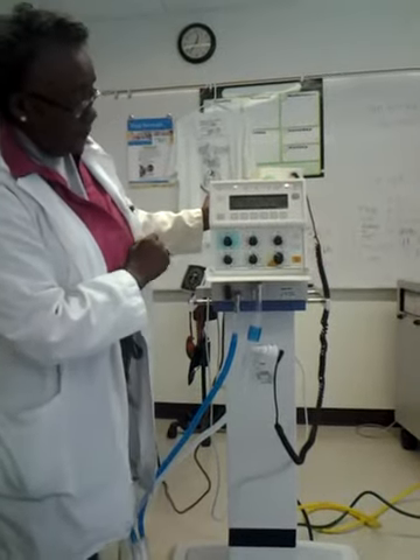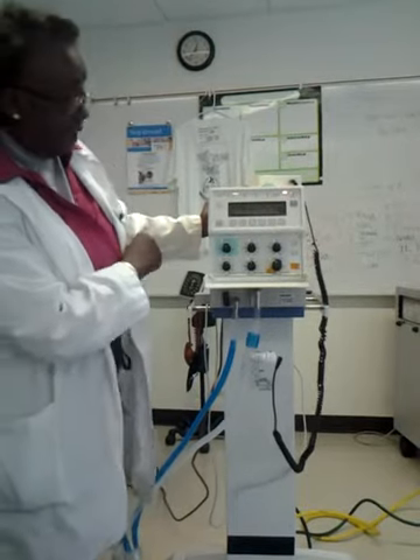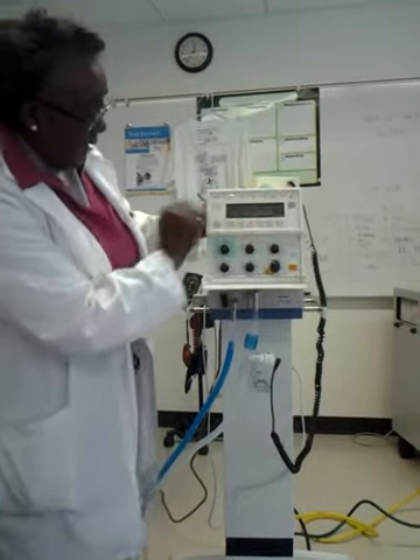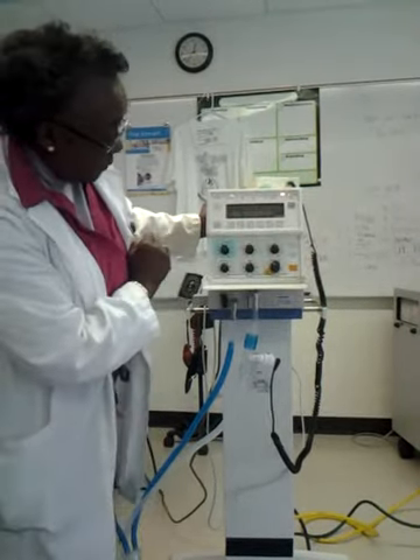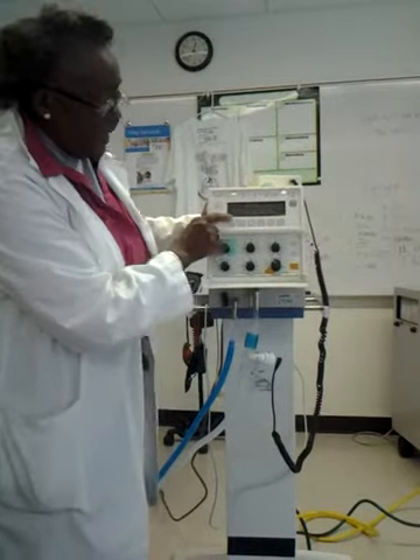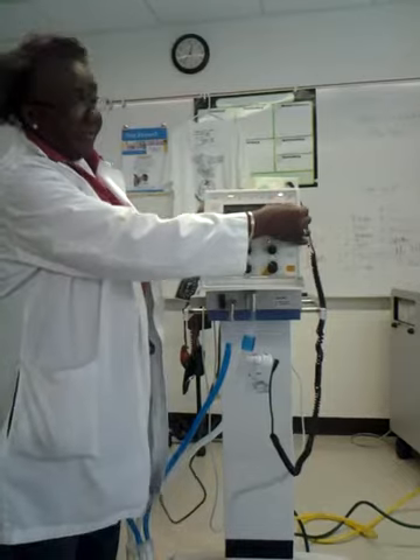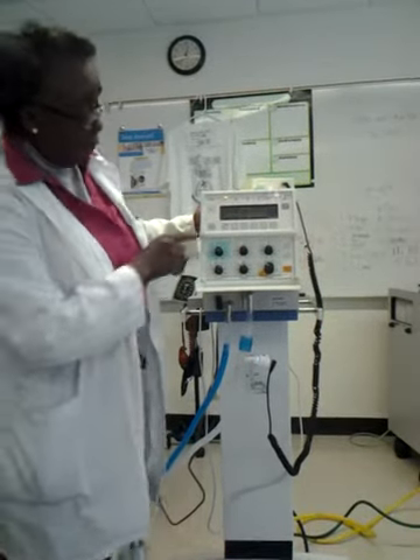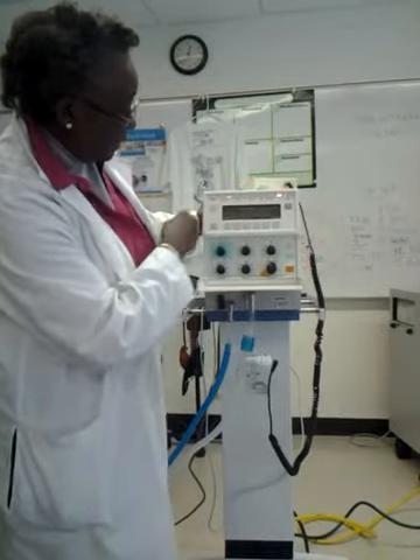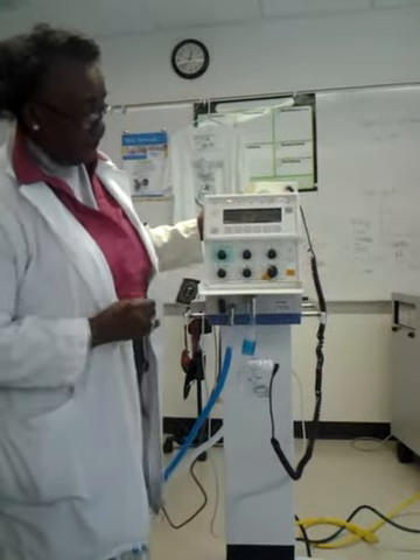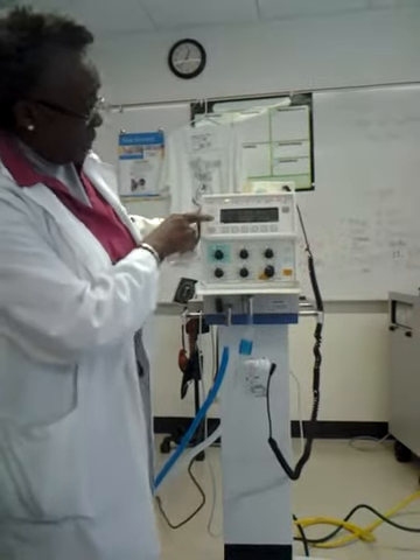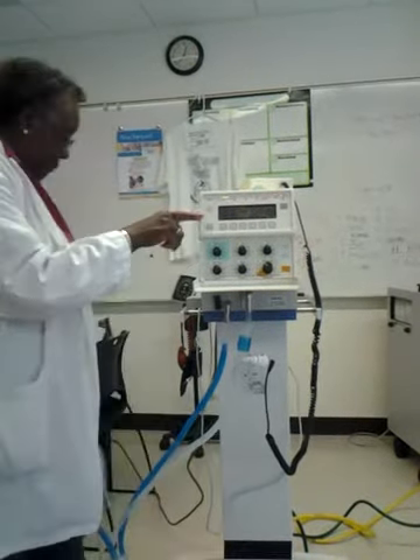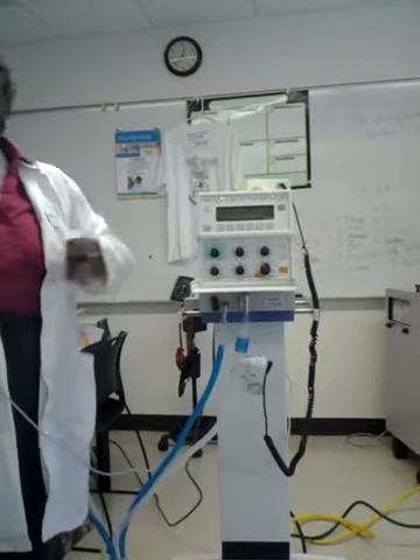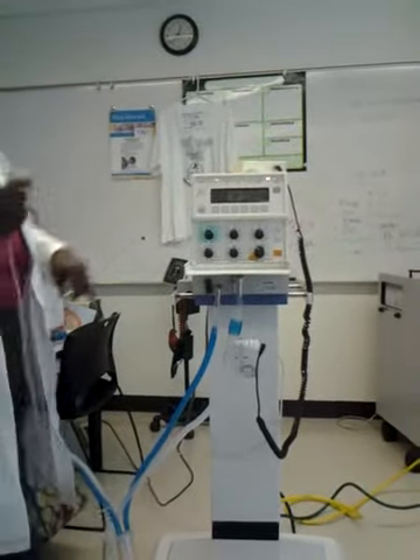Your modes are very easy. You just press modes and it comes across the bottom down here and tells you which mode you want to get. This is your back arrow, and if you want to look at your graphs, you hit graphs. And then it asks you, do you want to look at your pressure waveform or your flow waveform? You choose which one you want to look at. Right now we're looking at the pressure waveform, or I can switch it to the flow waveform. But you notice I don't have a flow waveform because I don't have my flow sensor in line. So there's no flow waveform on the screen. If I put my flow sensor in line, then I can also look at the flow waveform.